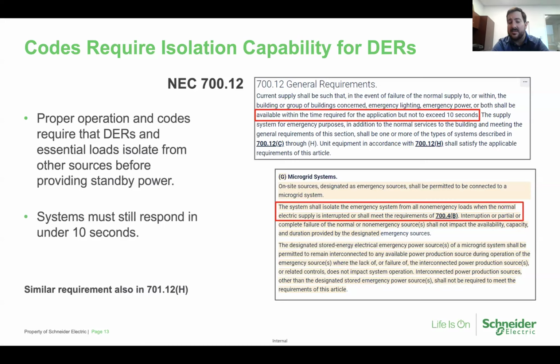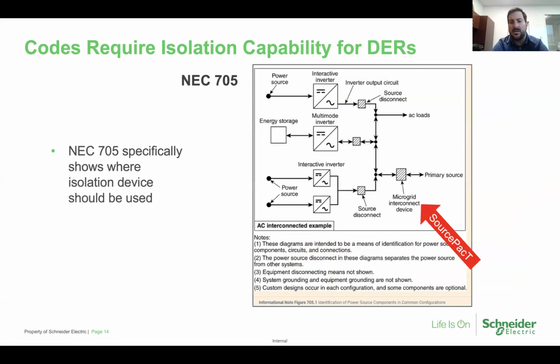Beyond that, that isolation function still has to happen within 10 seconds, as you can see on the top here, for those who are working in Article 700 type loads that have more stringent requirements on how quickly they have to be online and feeding power to those critical loads. Next slide. Here is an example of how that interconnect or isolation device would fit into the system.